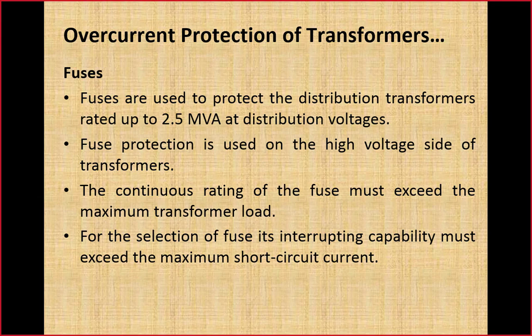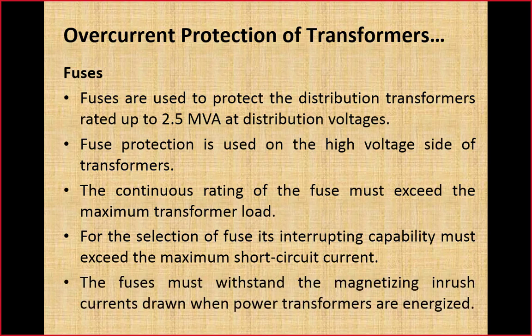So in chapter number 4 we have discussed three loading ratings of the fuses: continuous load, hot load pickup and cold load pickup. These pickup values of the fuse describe this high current at the time of energization of the power system, immediately after tripping and after a delay of 30 minutes. So fuses must withstand the magnetization inrush current drawn when power transformers are energized.